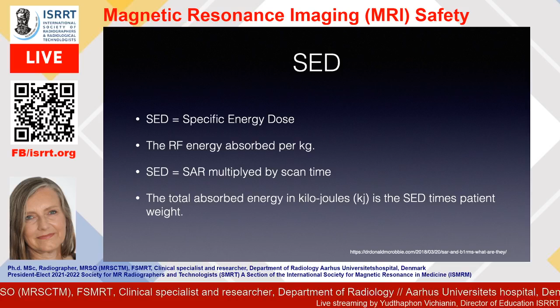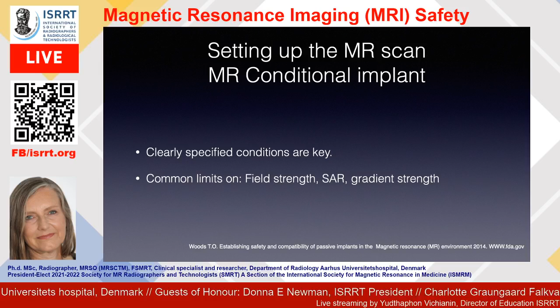So, setting up the MR scan when you have an MR conditional implant. Here what's really important is clearly specified conditions. And the common limits we'll see described are mainly on field strength, on SAR and gradient strength. And it of course can be very challenging, but today the vendors are producing tools that can help us perform safe scanning when we scan patients with conditional implants. And here you can see some examples. You can simply put in the values that you find in the documentation of an implant, and the scanner will do the job for you so that you don't exceed any of the limits.